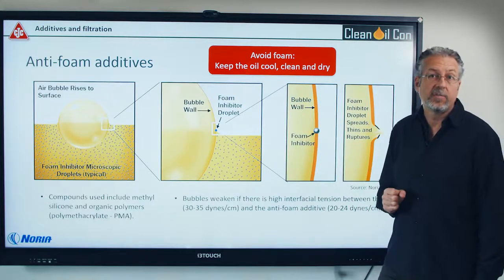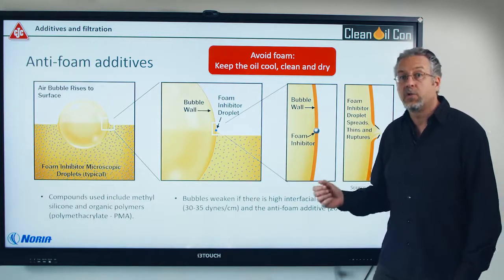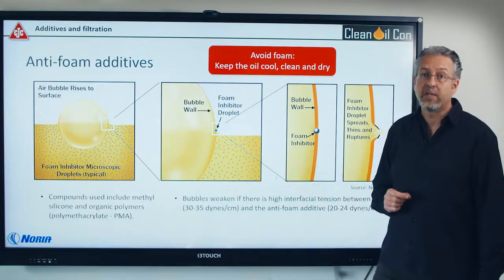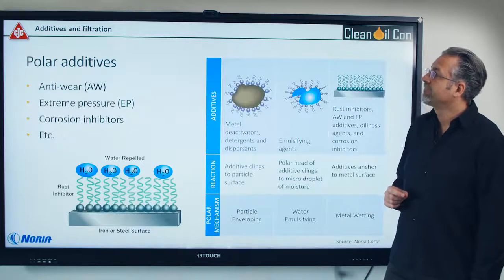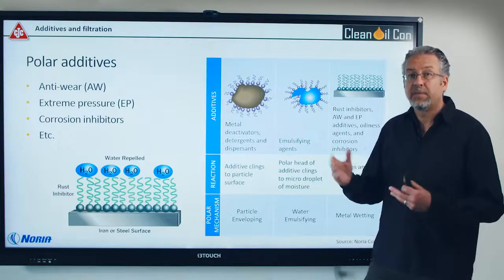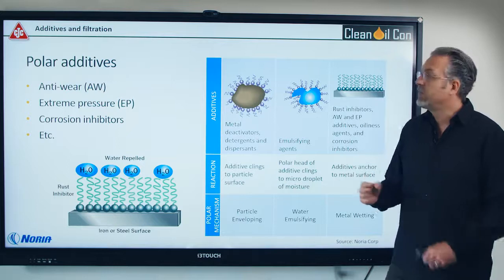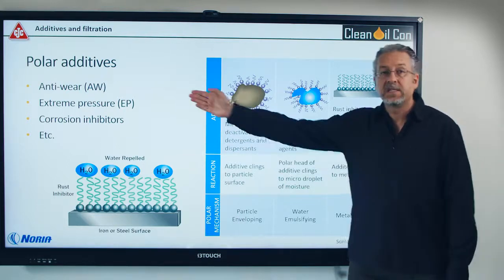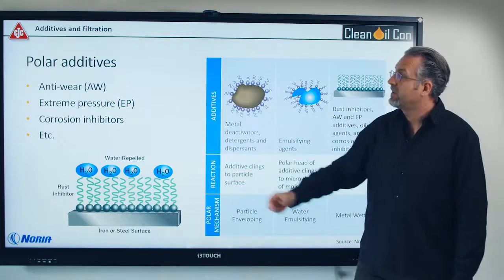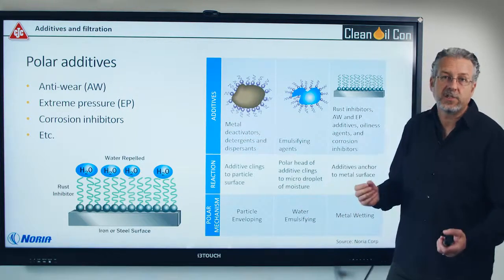So if you keep the oil cool, clean and dry, there's actually much lower risk that the oil is foaming because bubbles are seeding onto dirty oil. If you're afraid that you'll be losing too much of your anti-foam additives over time, you should go for the PMA or the polymethacrylate ones. Secondly, we have polar additives. These are designed to help your machine at startup, so they cling onto the machine surface when you're starting up the machine. This includes ZDDP anti-wear, extreme pressure additives, sulfur phosphorus, and corrosion inhibitors.